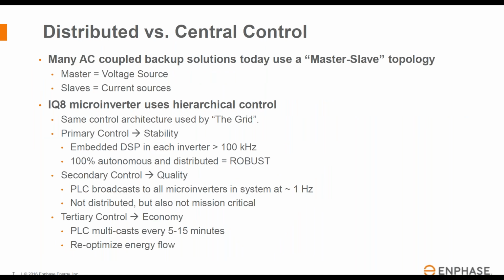One of the things we think a lot about at Enphase, because we make lots of little things, is how to control many little distributed things versus a centralized control. Historically, when you had a backup power solution, it was very common for them to be AC coupled, where you have multiple inverters connected together on the AC power system within the facility. The common approach was a master-slave topology, where one master essentially established the voltage, and multiple slave sources, which were current sources, followed the lead of the voltage source device. We don't do it that way.